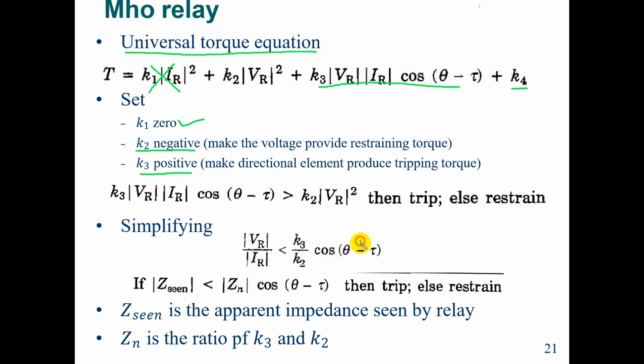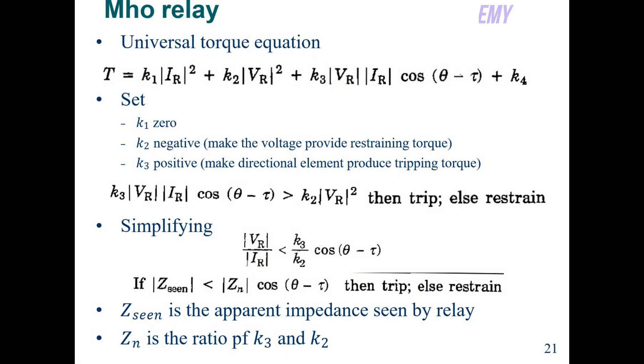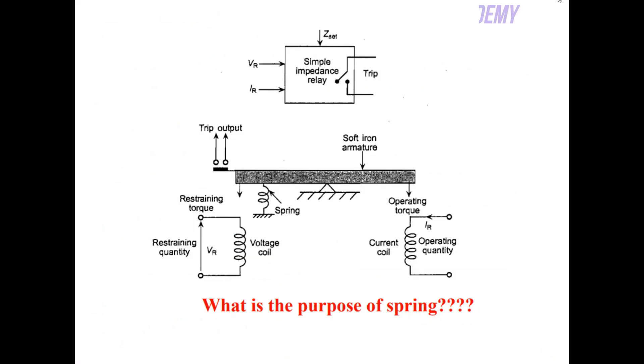Vr divided by Ir is the apparent impedance Z seen by the relay, and Z_n is the ratio k3/k2 × cos(θ − τ). If this condition is met, your relay will trip; otherwise it will restrain. Now let's talk about the beam. This is the restraining coil and this is the operating coil. This is the torque due to the directional components and this is the torque due to the voltage.